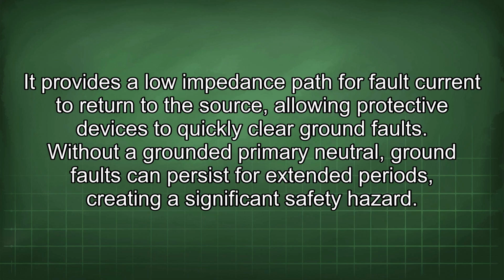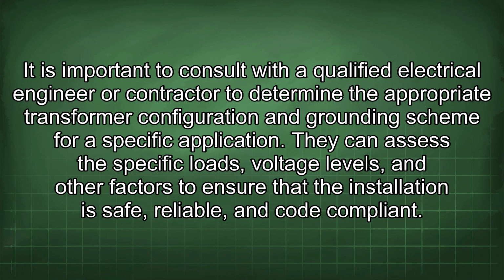It provides a low impedance path for fault current to return to the source, allowing protective devices to quickly clear ground faults. Without a grounded primary neutral, ground faults can persist for extended periods, creating a significant safety hazard. It is important to consult with a qualified electrical engineer or contractor to determine the appropriate transformer configuration and grounding scheme for a specific application.